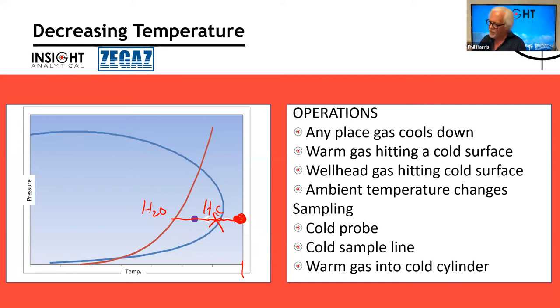We had this issue show up in one of our installations with a client. Great installation, analyzers installed well, heat trace on the sample line, but no heating around the probe. So in wintertime, the probe gets cold, ice forms in it. Then when it warms up in the daytime, that ice starts to give off water vapor and you read an arbitrarily high dew point.